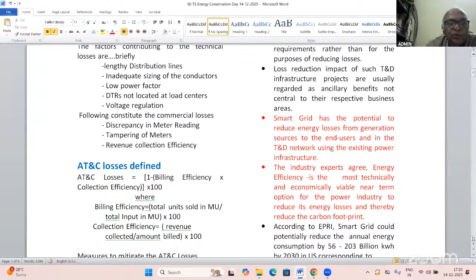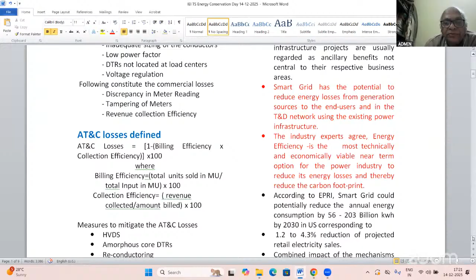AT&C losses are defined as 1 minus billing efficiency into collection efficiency, into 100. Billing efficiency is total units sold in million units divided by total input in million units. Collection efficiency is the revenue collected divided by the amount billed. That's how AT&C losses are defined.